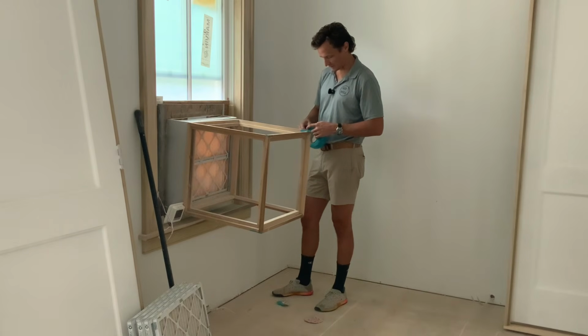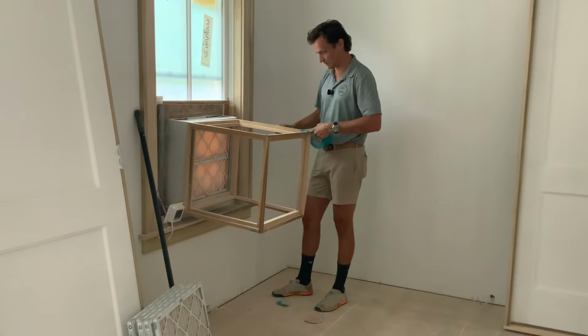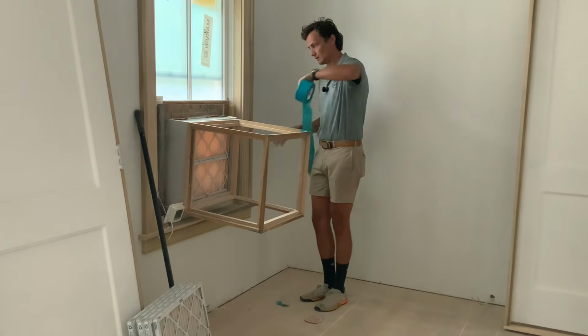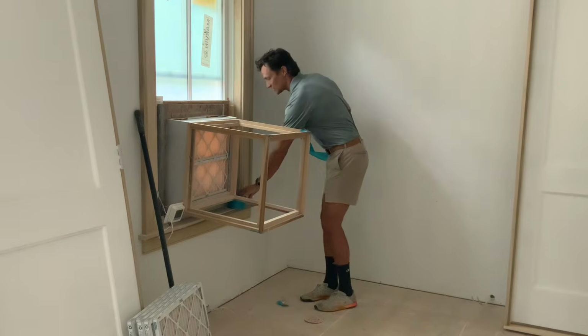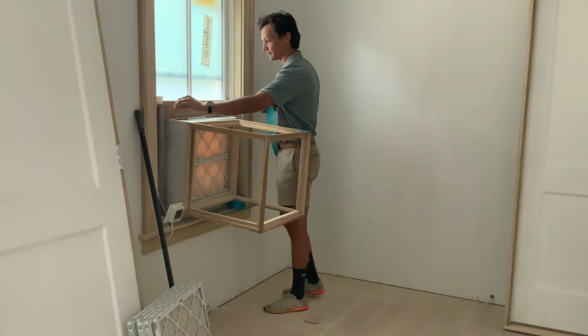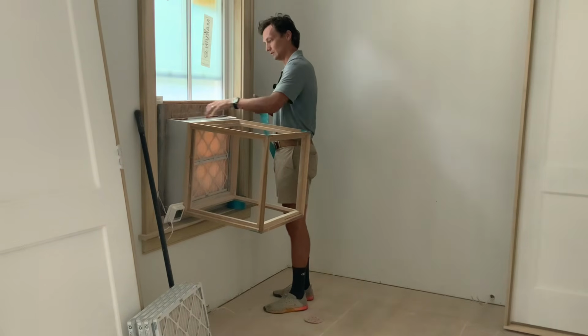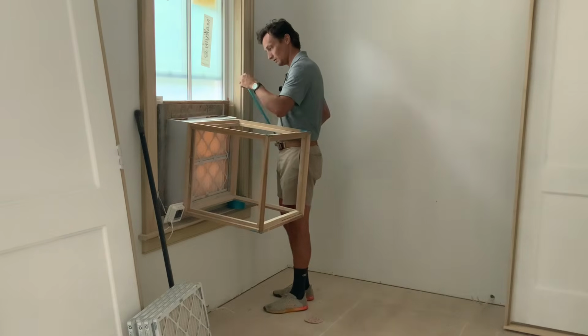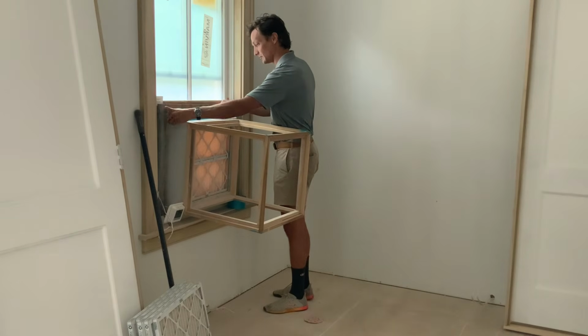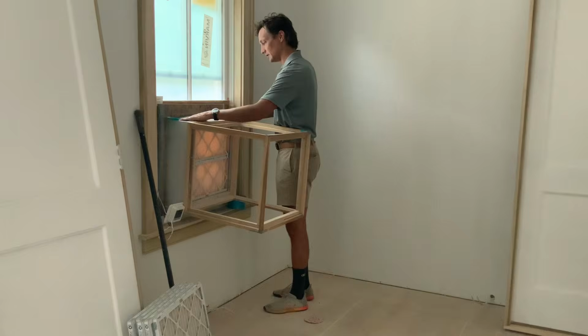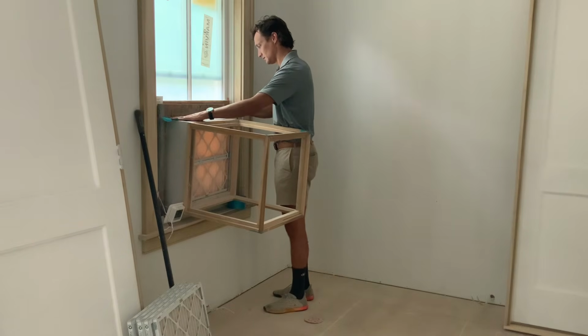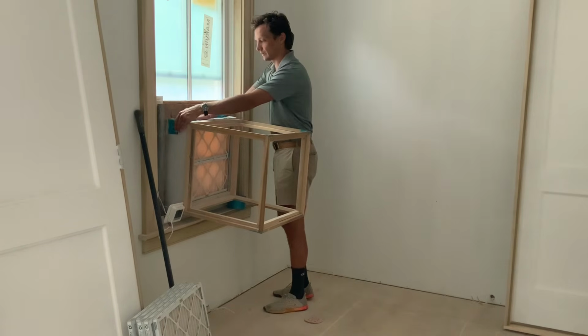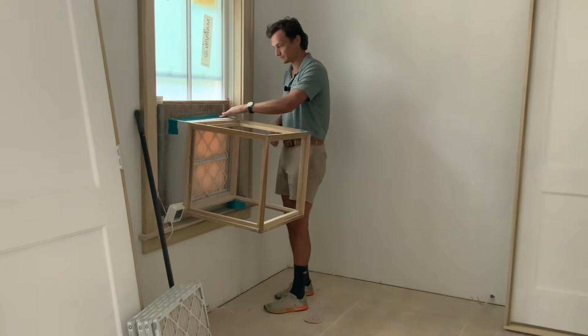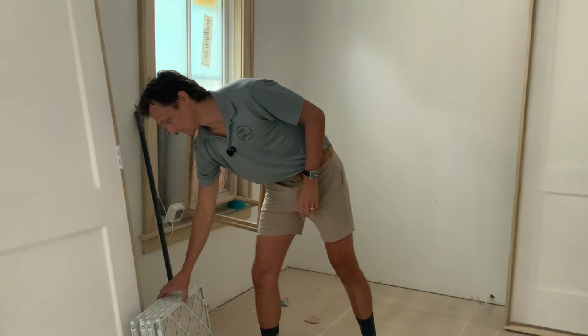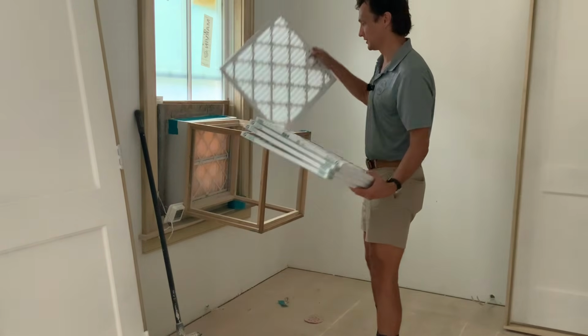In the 4-inch filter box, take a nice fat strip of duct tape, and we're sealing the back edge of the filter box. There's a gap up here, and we want to make sure that dirty, dusty air is not able to sneak in there and get into our machine. Okay, make sure that's nice and sealed off, nice and tight. The 1-inch filters go onto the box. Again, metal side down.